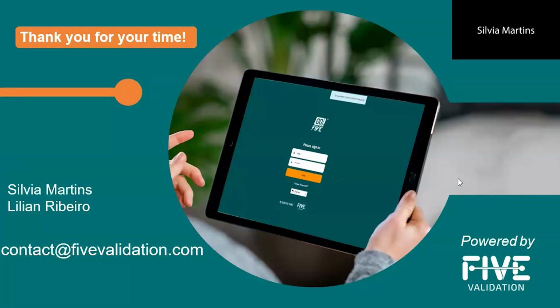So if we are going to embrace this kind of calculation, or we are going to have some interface from CDS with LIMS, for example, we definitely need to classify it as category 4. So it really depends. If you are using very, very standard functionalities, in our opinion, it's going to be classified as category 3. Why am I saying that it is our opinion? Because I should say, according to guideline X, it needs to be classified as X category, okay?